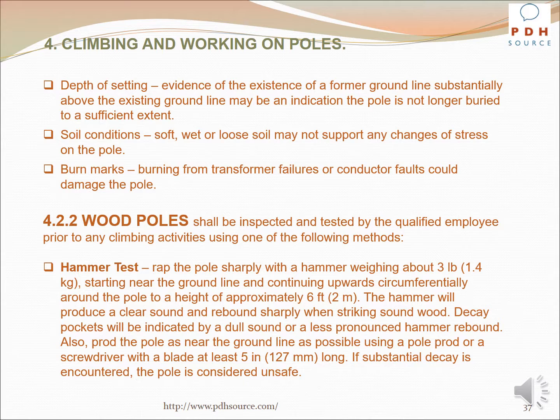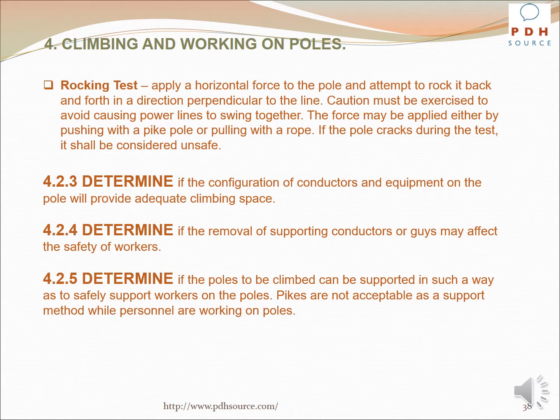Also, prod the pole as near the ground line as possible using a pole prod or a screwdriver with a blade at least 5 inches long. If substantial decay is encountered, the pole is considered unsafe. The rocking test. Apply a horizontal force to the pole and attempt to rock it back and forth in a direction perpendicular to the line. Caution must be exercised to avoid causing power lines to swing together. The force may be applied either by pushing with a pike pole or pulling with a rope. If the pole cracks during the test, it should be considered unsafe.